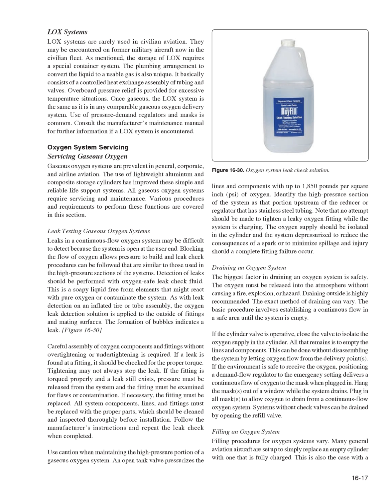Detection of leaks should be performed with oxygen-safe leak check fluid. This is a soapy liquid free from elements that might react with pure oxygen or contaminate the system. As with leak detection on an inflated tire or tube assembly, the oxygen leak detection solution is applied to the outside of fittings and mating surfaces. The formation of bubbles indicates a leak.